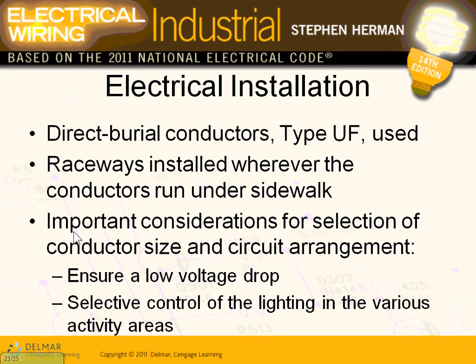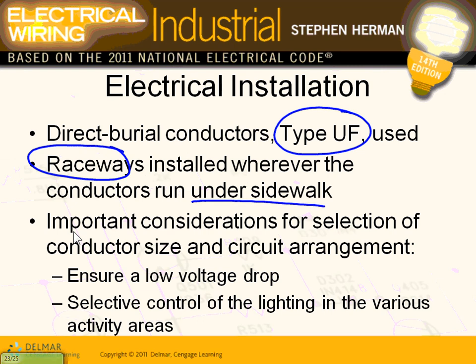When you do installation, there are two ways of installing the sites: either direct buried cable — that would be a UF cable, direct buried — or conduits and raceways. One thing — even if you use a direct buried cable, every time you go under a sidewalk or under a building, you always have to put conduits. Why? Because it's easier to move them — you don't need to bust the sidewalk to get to the cable if it's faulty. For conduits, you don't want to put anything less than two inches underground.